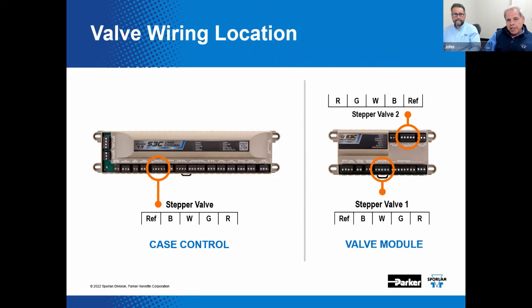Yeah. Now, this slide details the location of the termination points for step motor valves on both the case control and the valve module. Now you'll note that here in the slide, we refer to them as stepper valves. Here is the case control with stepper valve termination points for the black, white, green, and red wires. Also, we have the valve module, which is essentially an extension of the case control. And likewise, we have stepper valve 1 and stepper valve 2. Right. The first evaporator control lands on, the wires would land on the case control, as we've shown here.